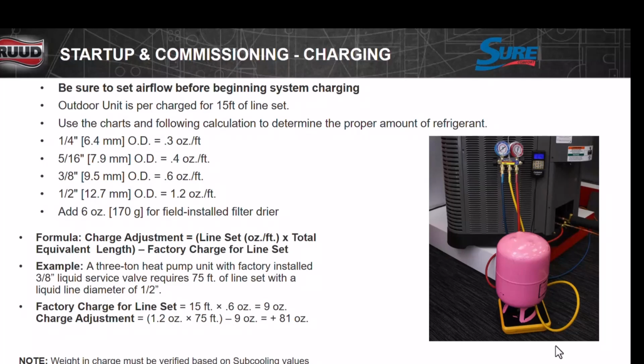When you open up the line set, open the liquid line first. Let all that liquid flow out of the condenser through the liquid line like it's supposed to, and then open up the suction line. At that point, I would turn the system on, and I would not weigh anything in. I would use the charging chart to verify the charge at that point. Okay, you still can weigh it in, but remember, we're dumping liquid in there, and we don't want to do that.